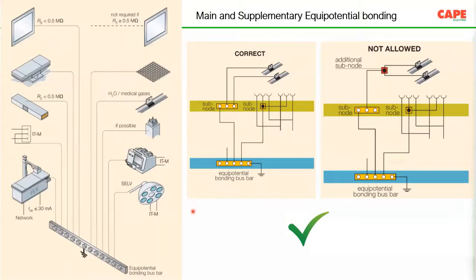As I am showing in this picture, the correct way of earthing is called main equipotential bonding and supplementary equipotential bonding. Main equipotential bonding, as you can see in the picture at the center: at the mains incoming panel, we are supposed to make an earth bus bar, and the exposed and extraneous conductive parts must be connected to this bar. Then at the sub node, for example the operation theater, you are supposed to have supplementary equipotential bonding. On the left side, you can see how the supplementary equipotential bonding is made.